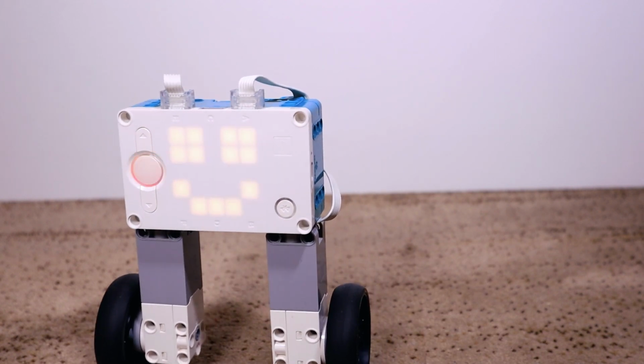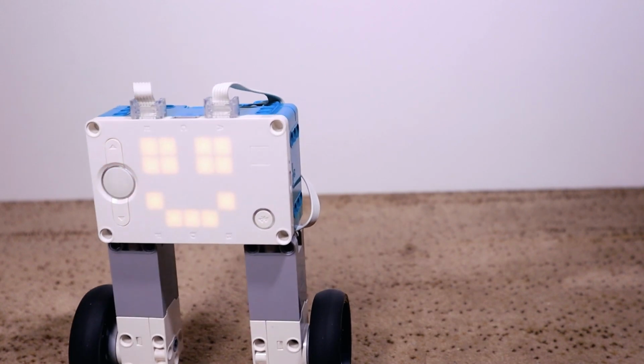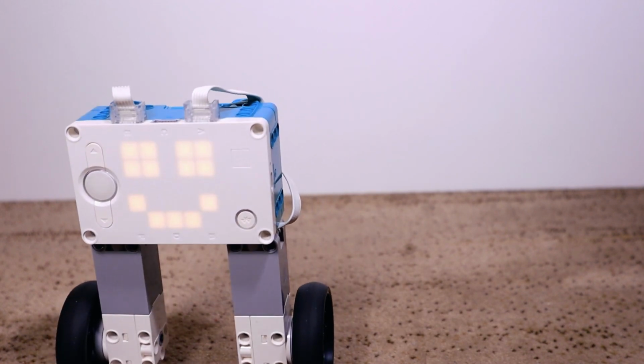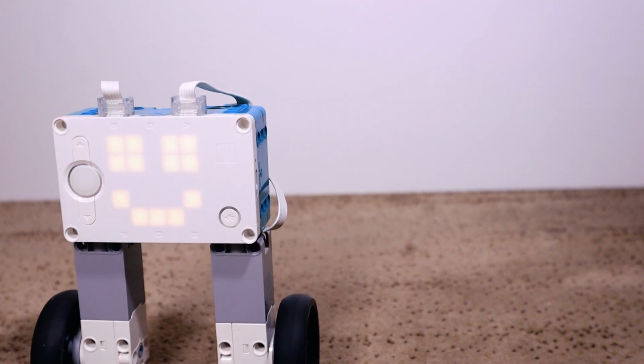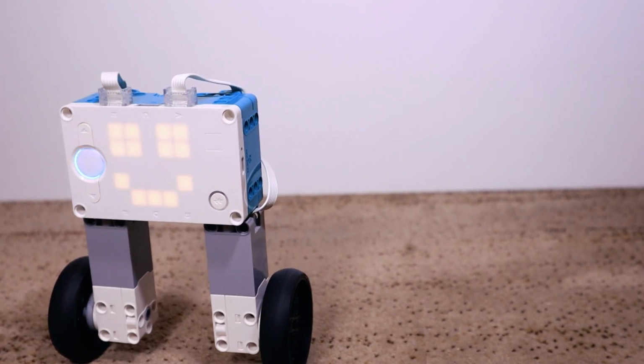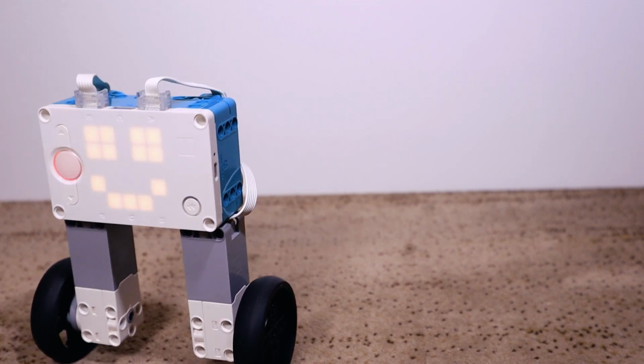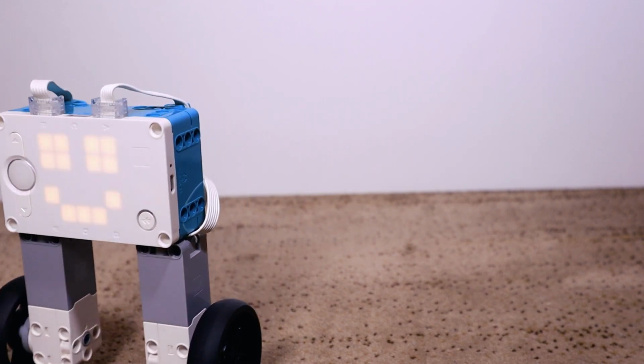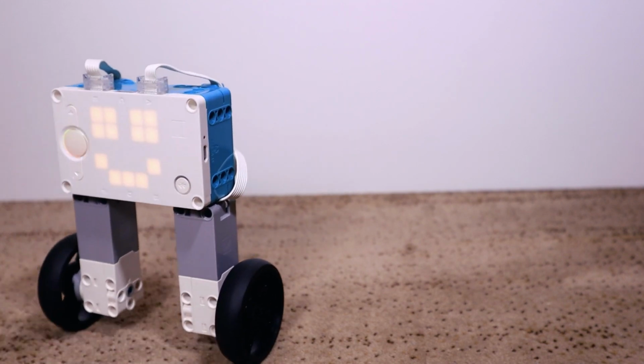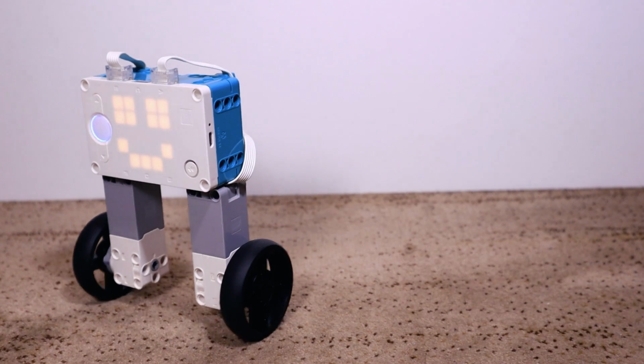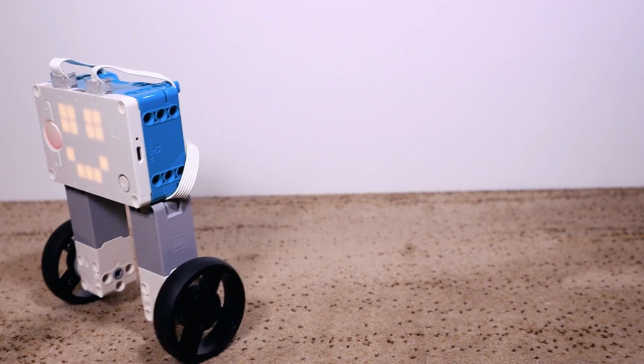So if you are moving the robot during this calibration in any way - if you just punch the robot or you're spinning it on a turntable - you're going to miscalibrate your gyro sensor. It's going to have an incorrect baseline for how much acceleration it needs to figure out, and it assumes that additional acceleration you just added is part of what it needs to filter out. Any measurement your gyro sensor makes after that is completely bogus and unusable. This is because the gyro sensor measures angular rate of rotation, and the Earth's rotation gets measured as part of that, which is why it needs to be filtered out.